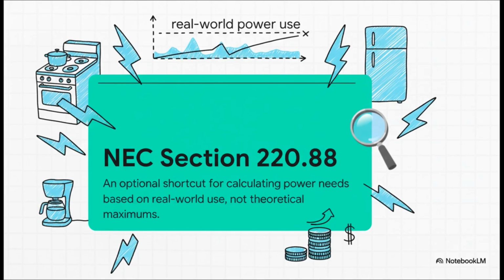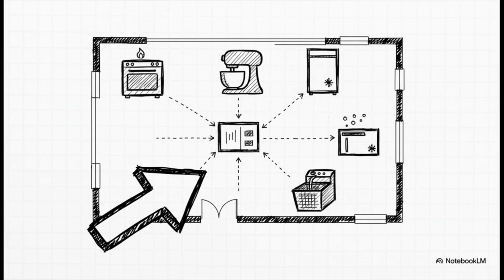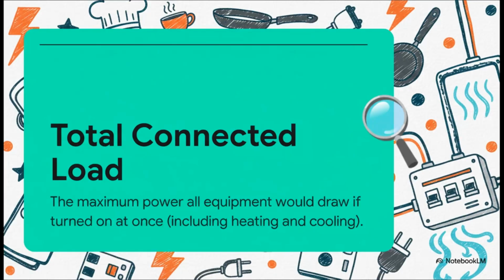Well, think about it. Neutral sizing is all about system balance, right? And potential harmonics from things like electronic ballasts or VFDs. The 220.88 shortcut is great for predicting total power demand, but it doesn't really see those tricky current interactions on the neutral. Ah, so it's a statistical shortcut for the hot legs, but for the neutral, where currents might add up weirdly instead of canceling, the code says, nope, use the standard, more detailed method. Exactly. It's balancing that high-level efficiency with fundamental safety physics. Fascinating distinction.